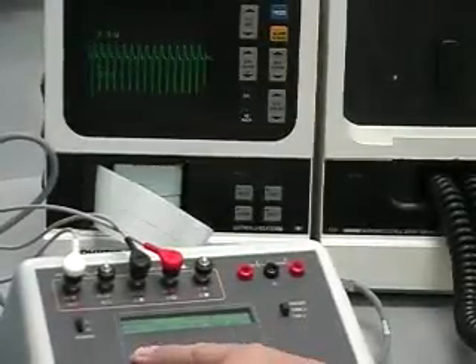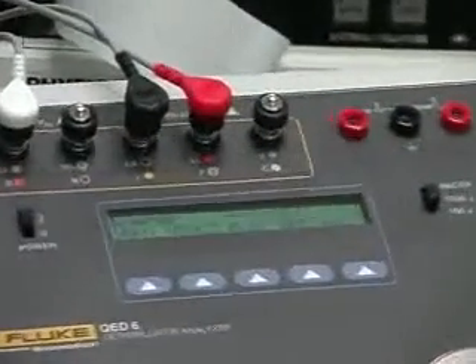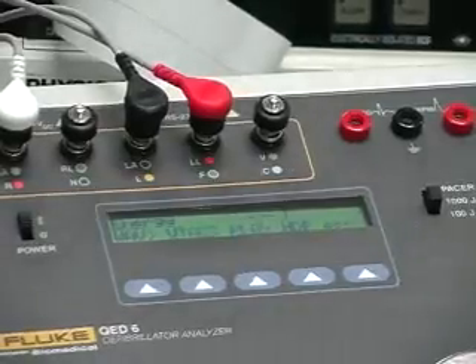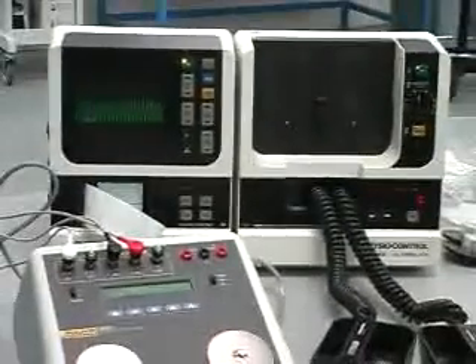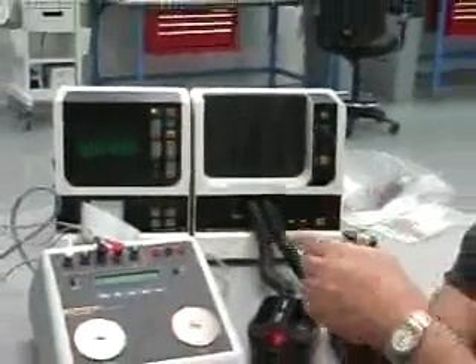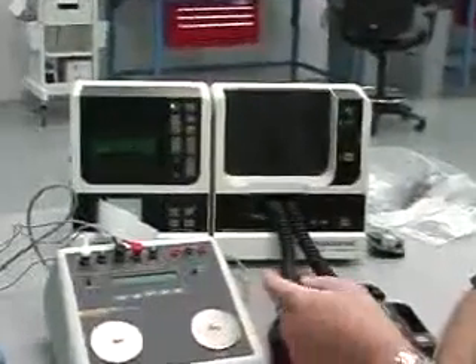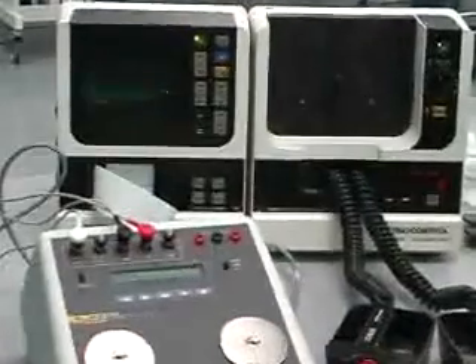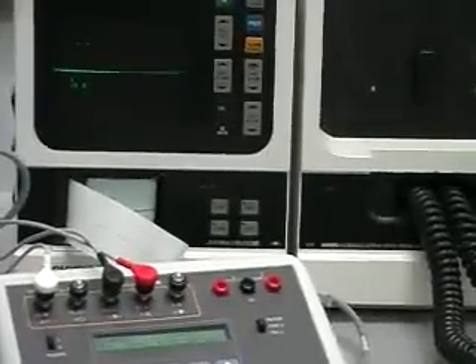Or the basic VTAC at a lower rate. Here's a higher rate VTAC, and then a VTAC 3, which, as we discussed a little bit this morning, is the polymorphic or irregular rate wide QRS complex VTAC, and this is the one you would use for testing the Philips FR2 style defib. It has a bit more of a random amplitude and a bit more of a varied R wave configuration. And then we also have a few waveforms in there for testing the automatic defibrillators to make sure that they do not discharge.